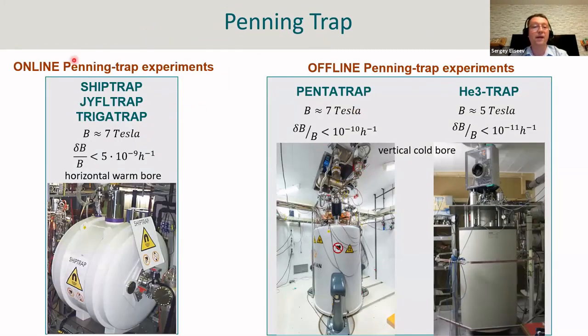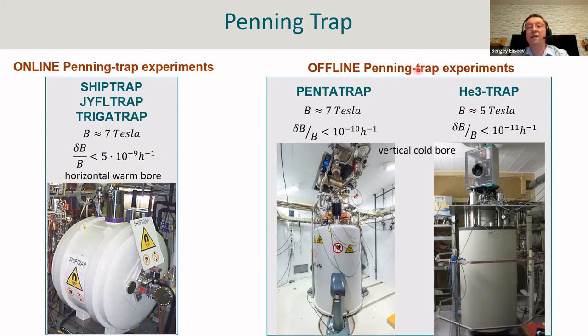Here are examples of magnets used in high-precision Penning trap mass spectrometry. In online experiments like ShipTrap, JYFLTRAP, and TRIGAtrap, one uses 7-Tesla superconducting solenoids with horizontal warm bore. Such magnets have two regions of homogeneous magnetic field, allowing two traps in one magnet. Relative magnetic field drift stability is typically better than 5×10⁻⁹ per hour, which is sufficient for online measurements. In offline experiments like PentaTrap, superconducting magnets with vertical cold bore are used. With additional measures, one can stabilize the magnetic field drift down to 10⁻¹¹ per hour — an extremely stable magnetic field.